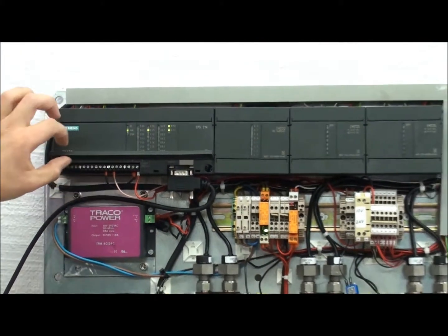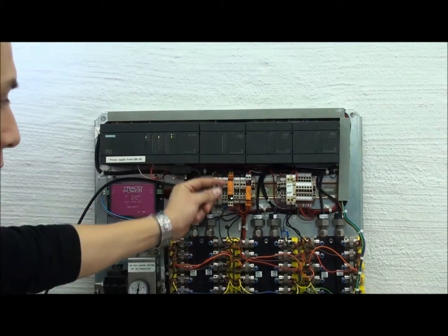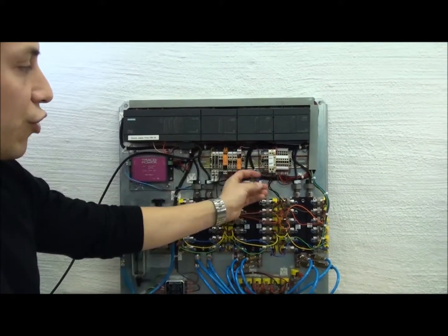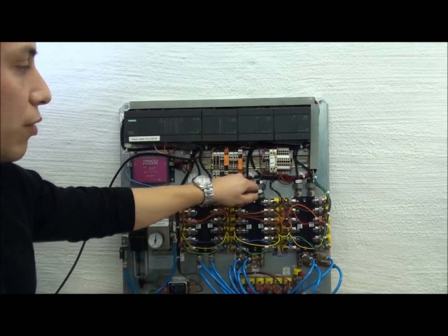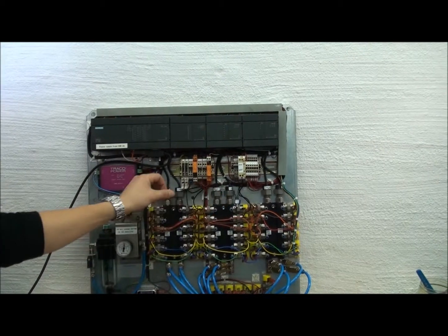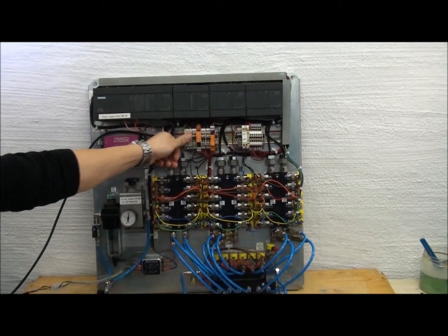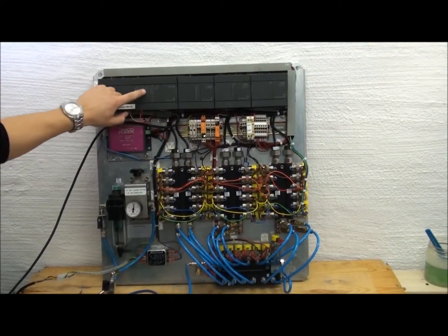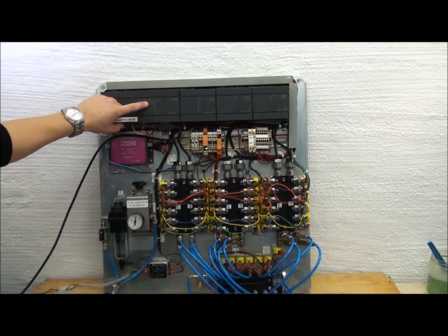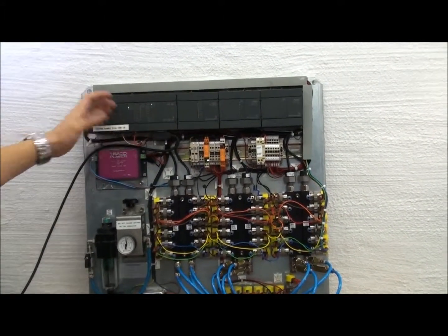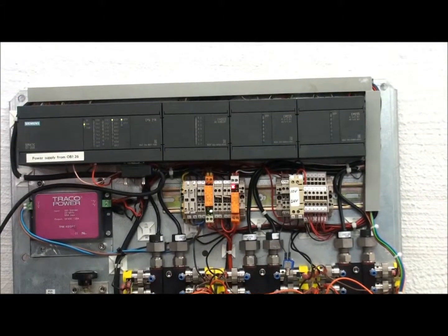Okay, I think 30 seconds has gone already. So then we break again. We change the switch back to the normal position, which is not connected, not jumped anymore. Then put the system on again, and then you see that the light is not lit anymore. And now the system should be up and running in the normal mode.